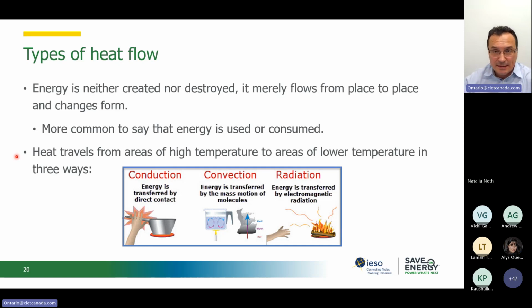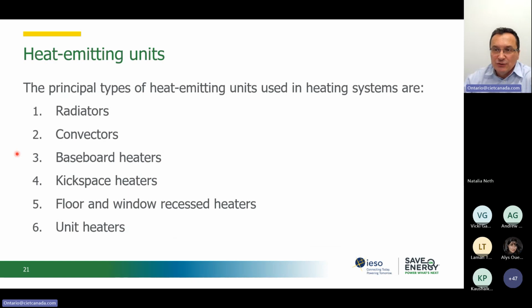We said that the majority of solutions are based on indirect heating mode, where we use some form of heat transfer. And you see that this heat transfer happens in 3 modes: conduction, convection, and radiation. Most of our equipment will have a combination of these 3 modes. Now, what we are interested in is enhancing one of these modes by designing heat exchangers. And based on which one we focus on, sometimes manufacturers will refer to those heat exchangers as radiators or convectors, to highlight what form of heat transfer is preponderant. But all of them will have some combination of those modes.